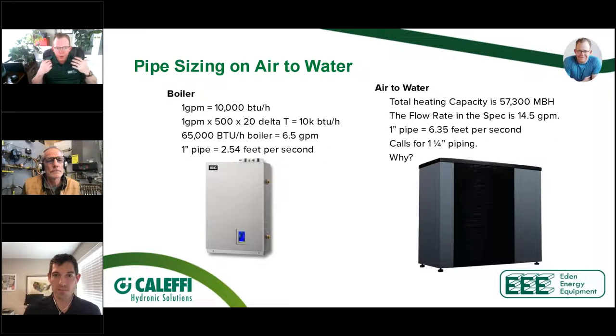So in my own house, I put everything in the CAD. Obviously, I have a lot of hydronic heat pump experience. And then I collaborated with the engineering team that designed the air to water I put in my house. And at the end of the day, my unit is 57,000 BTUs, and the actual flow requirement for that unit is 14.5 gallons a minute. I'm going to move quickly through this math because we have a totally different training class where we talk about the math.